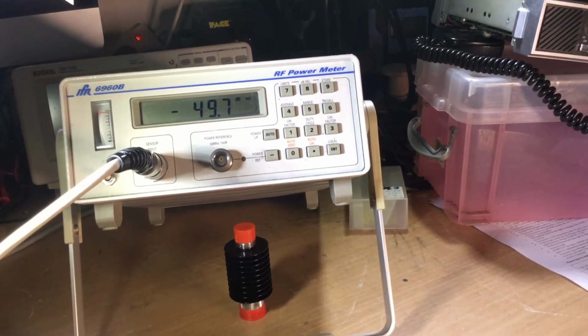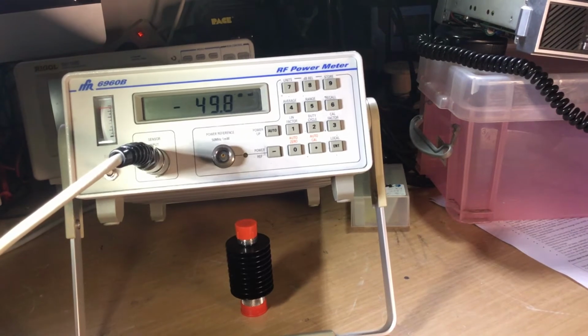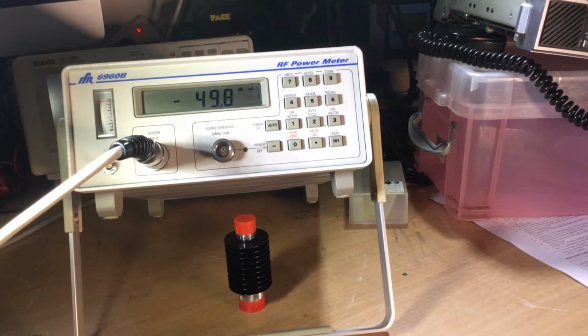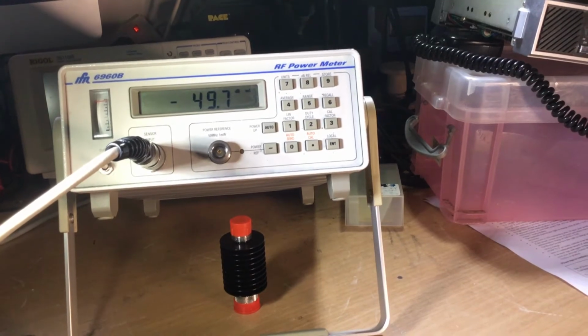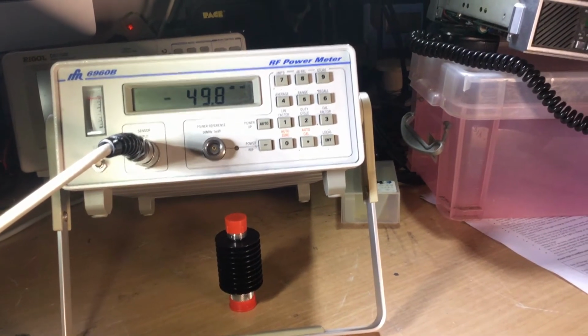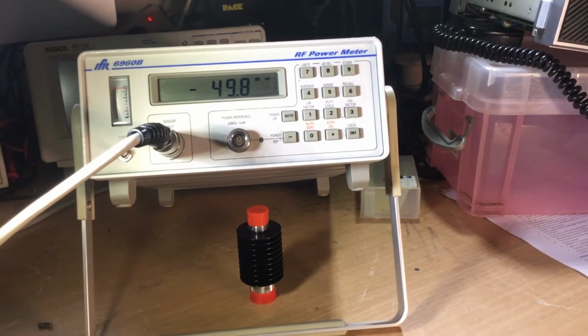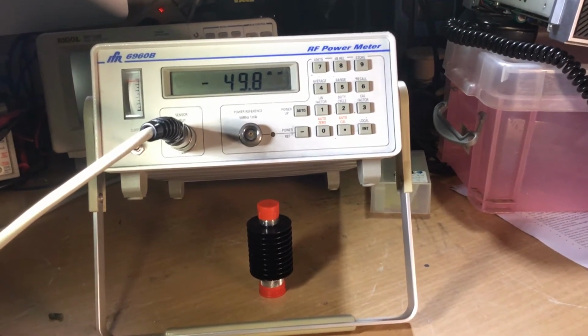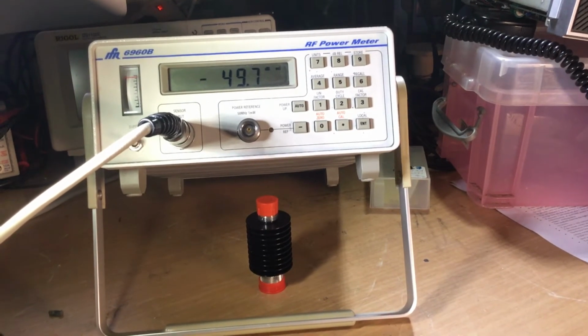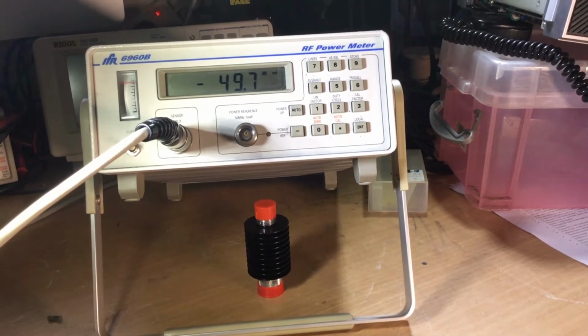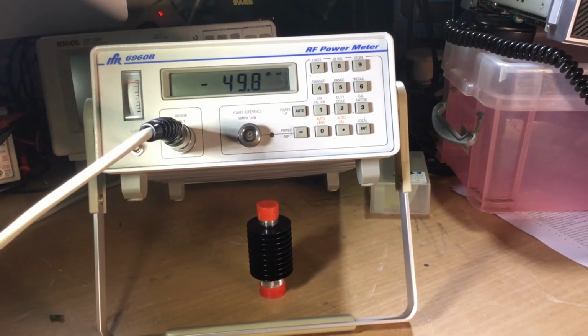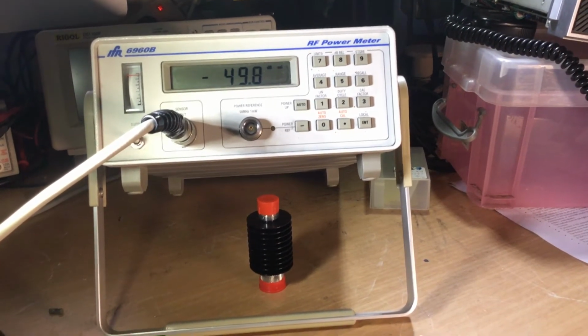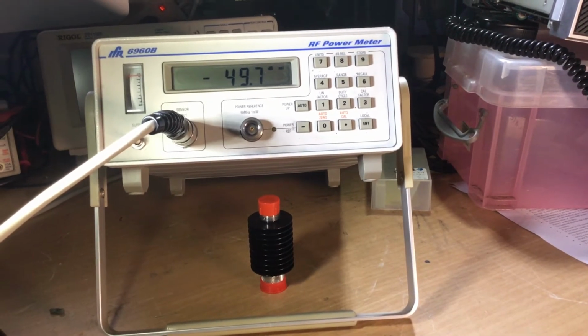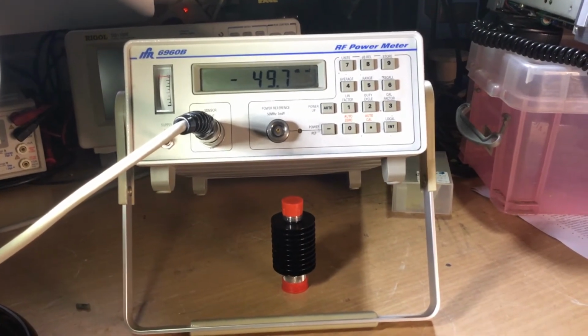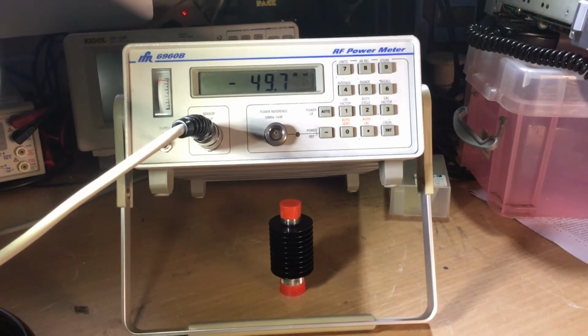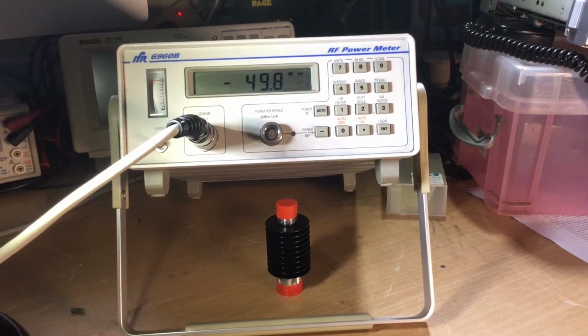Now it says here that there's an SRQ response to the system user. The SRQ response is always important, and in the 6960B the SRQs have been arranged to form a mask with each SRQ option having a binary weighting: 1 on end of measurements, 2 on error, 4 on end of GPIB operation. SRQ option 4 is used to inform the controller that the requested GPIB operation, such as auto zero, has been executed. Self-test is initiated when the instrument is switched on, and the validity of information in the non-volatile memory is automatically checked.